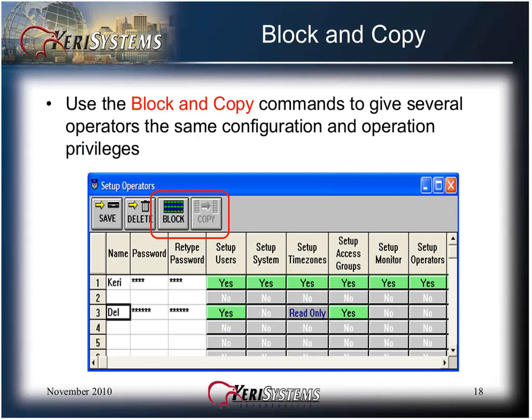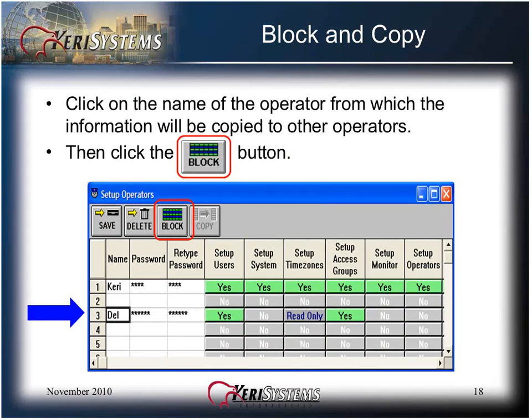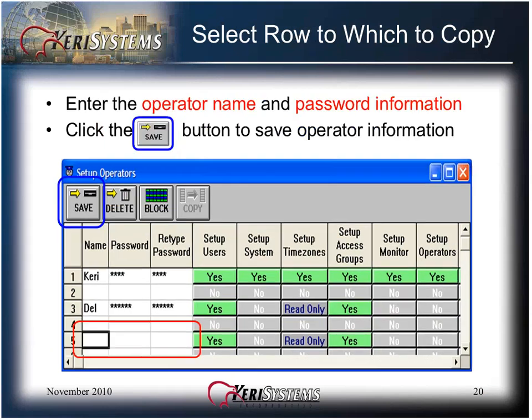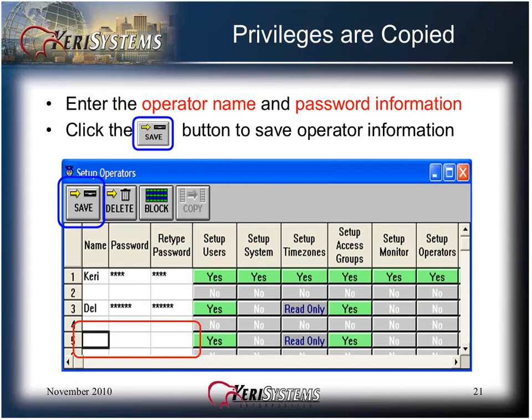Use the Block and Copy commands to give several operators the same configuration and operation privileges. This saves time in programming different operators with the same privileges. Select the operator by clicking on the name of that operator from which the information will be copied to other operators, then click the Block button. Click on the row to which to copy, then click the Copy button. Enter the different operator name and password information and click the Save button. This concludes Module 15 of 16, Setup Operators.